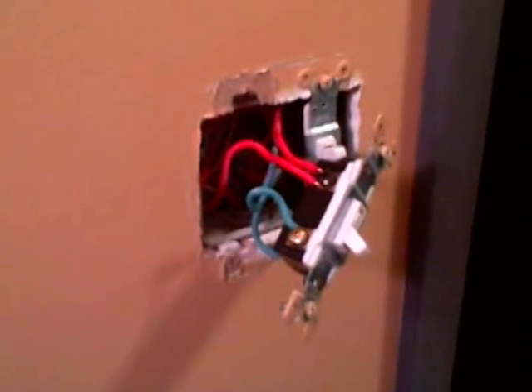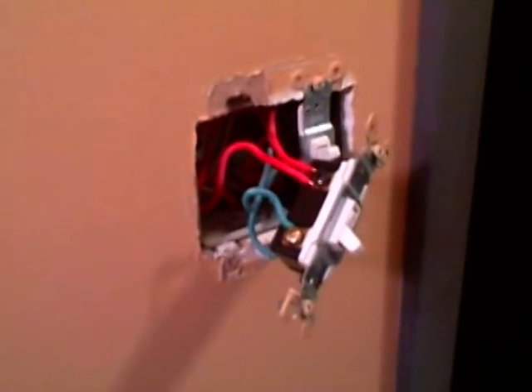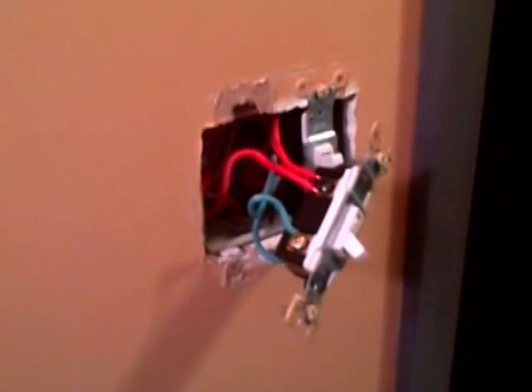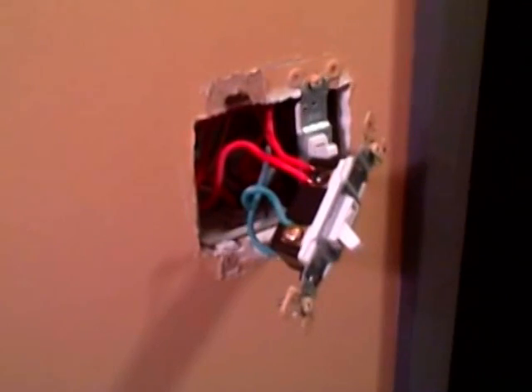Replacing a three-way switch is very easy if you haven't removed the wires from the old switch. Mark the common on both of the switches, then unscrew all your wires, reconnect it, making sure you connect the wire that was connected to the dark screw on both of the new switches and you'll have no problems. Now we'll go over troubleshooting tips if you've already removed your three-way switch and you don't know which wire goes to which terminal.